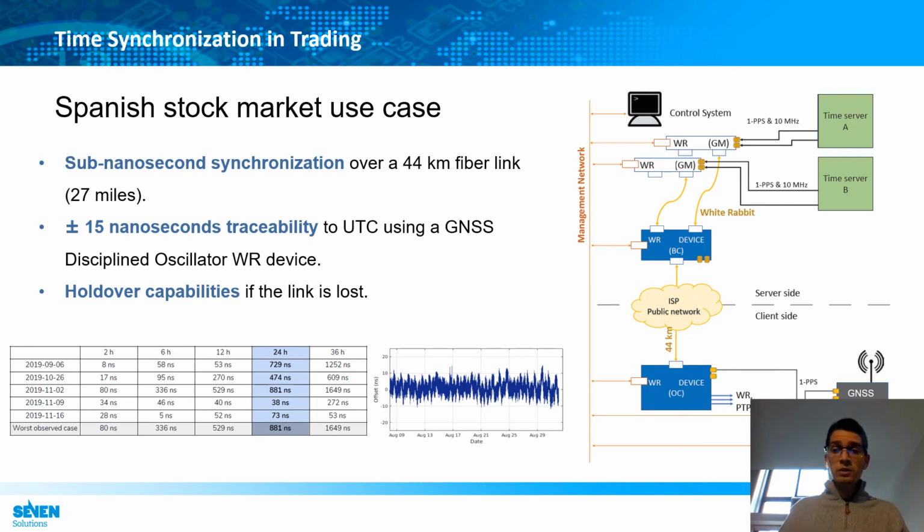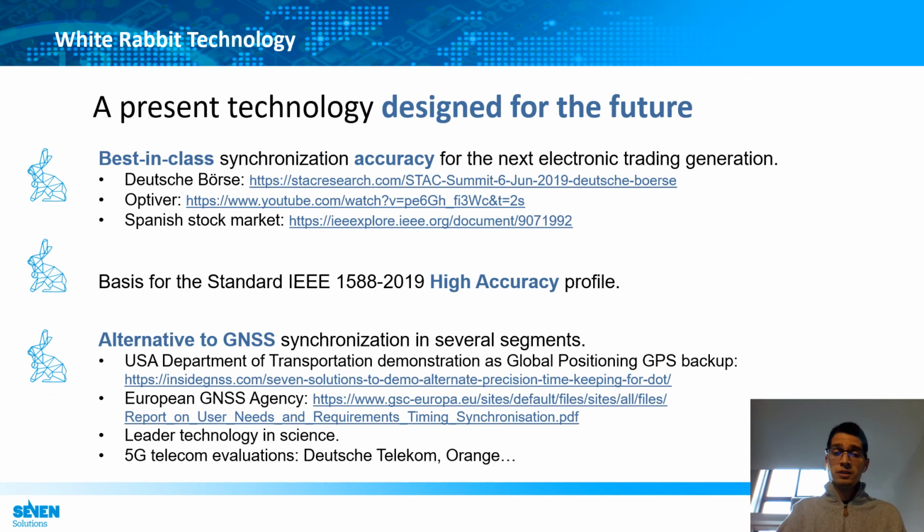A use case would be one in the Spanish stock market, where we synchronized different data centers using a 27 miles link, and we provided redundancy with a failover clock that ensures 1 microsecond after 24 hours, and also traceability using a calibrated GNSS White Rabbit device that was calibrated by a national metrology institute.